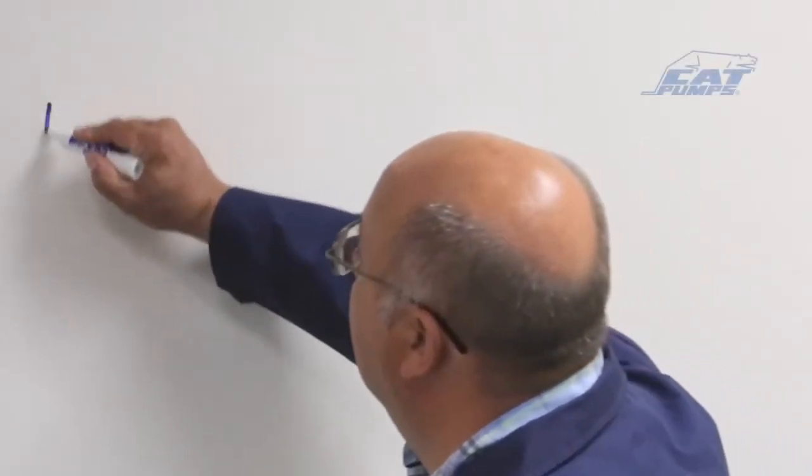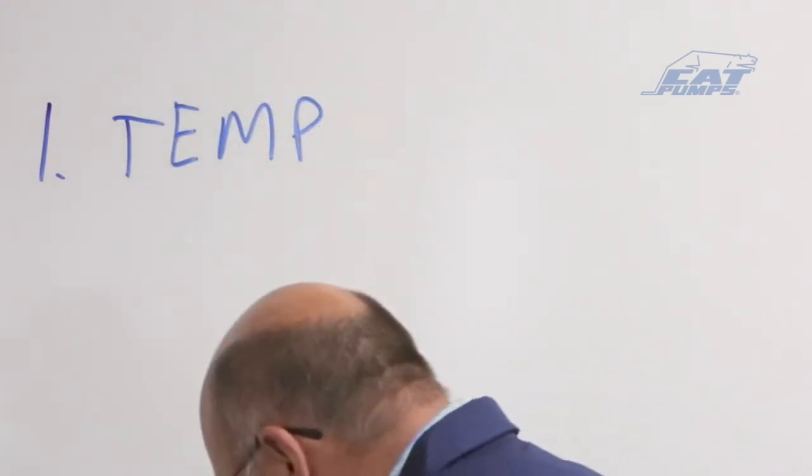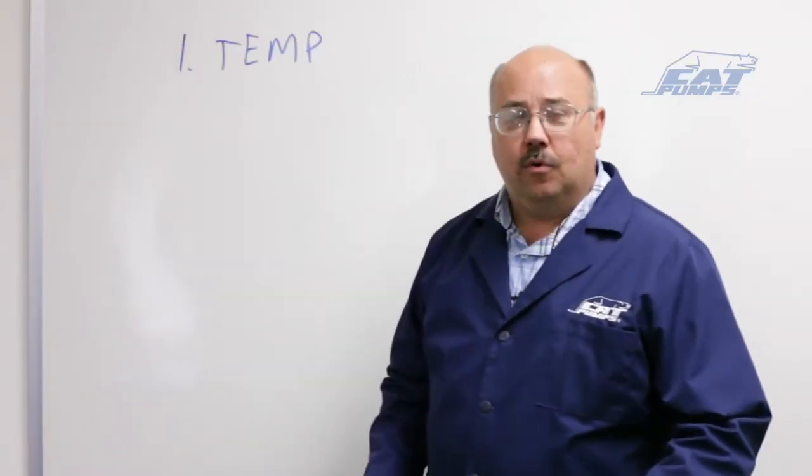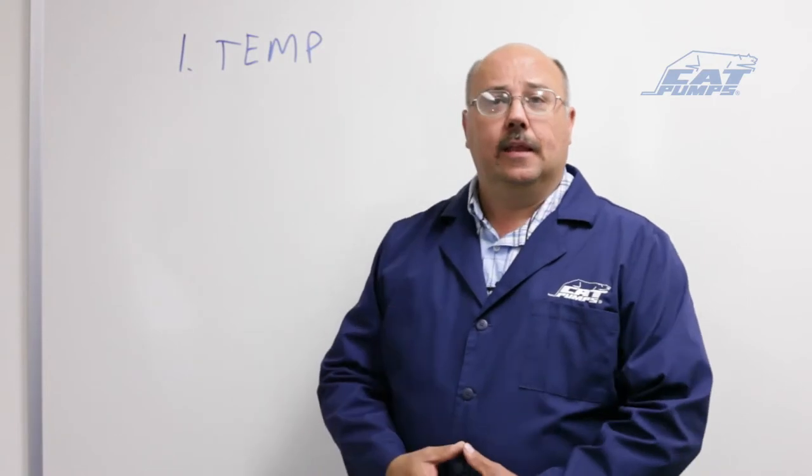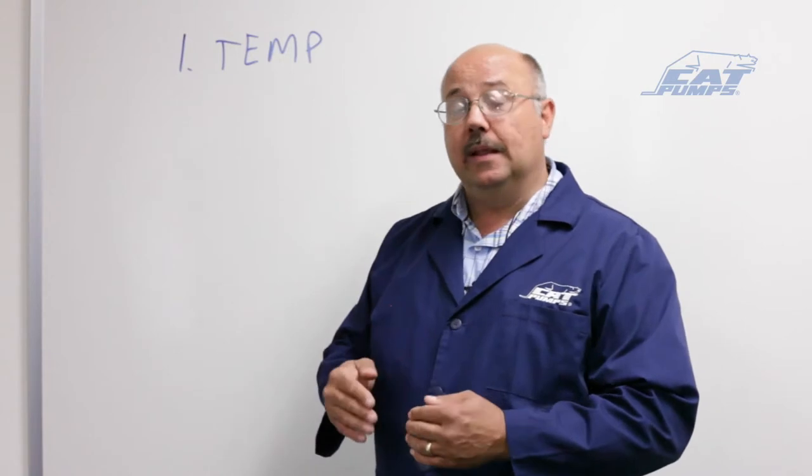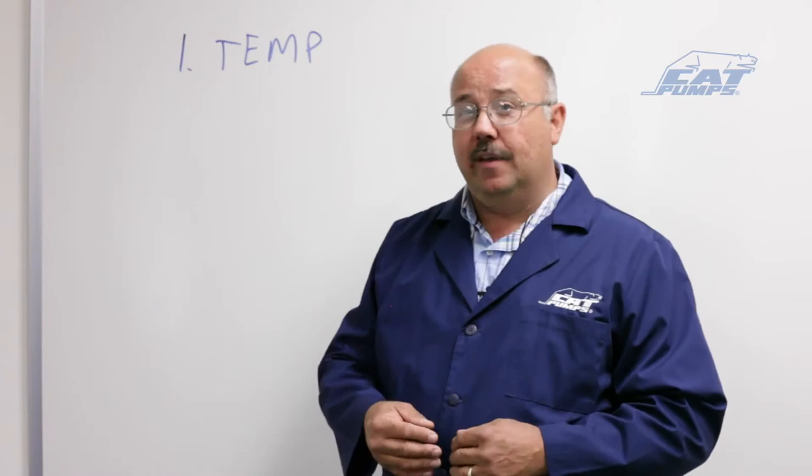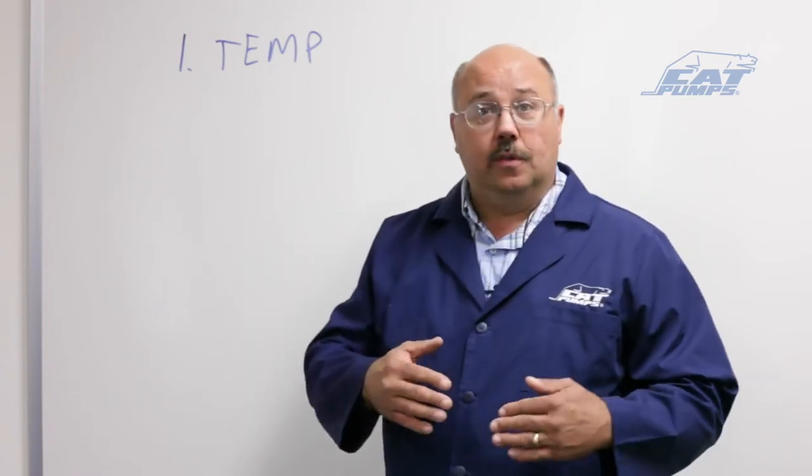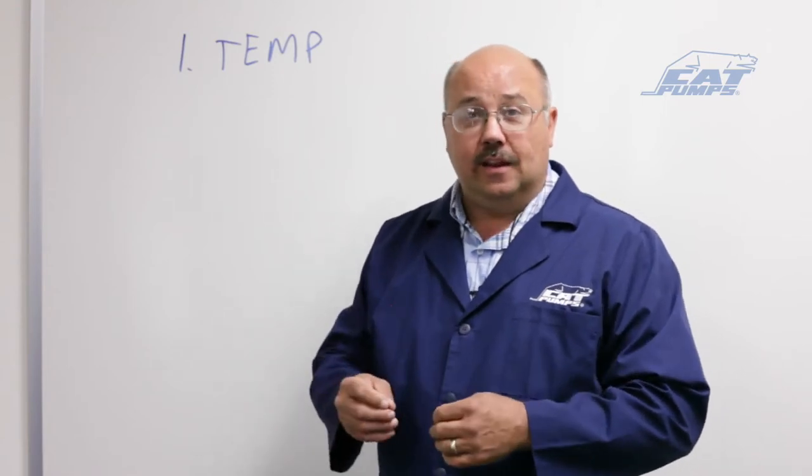One thing to start talking about is the temperature of the liquid that we're pumping. So number one is temperature. Water, of course, is a liquid because of its temperature and pressure. And if the temperature of water rises, it takes more pressure to keep it in its liquid state. So therefore, if we're trying to pump an elevated water temperature, the closer we are to boiling, the easier it is to have it cavitate in your pumping chamber.